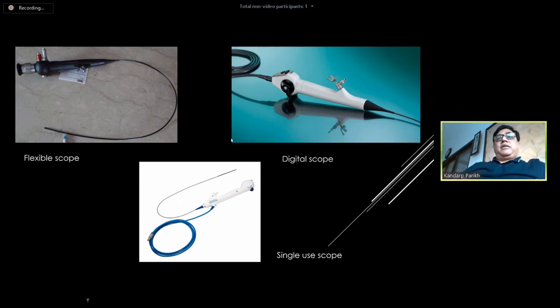And another advantage of this digital scope is that there is an inbuilt LED in the handle. So there is no separate connection for the light cable. And also here there is no separate camera. There is a cable which gets connected to the processor unit. So that makes these scopes lighter in weight, and also the handling of the scope is better, and the life of the scope is also more. But the only prohibiting factor with this digital scope is the cost, because you are buying a digital scope which is expensive. Also, you have to buy a processor unit or a hub. That is an image one hub in case of Flex XC, which is also very expensive.